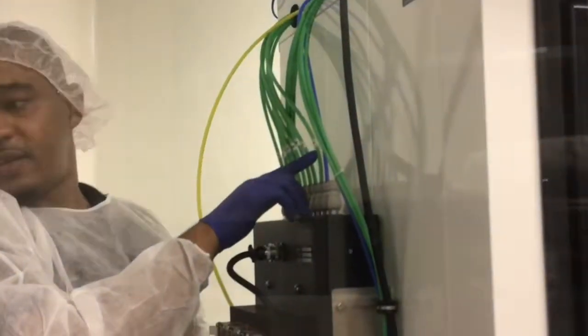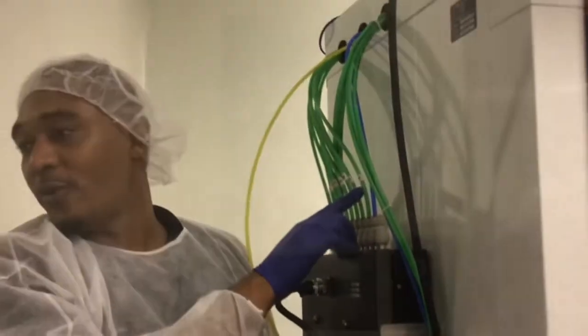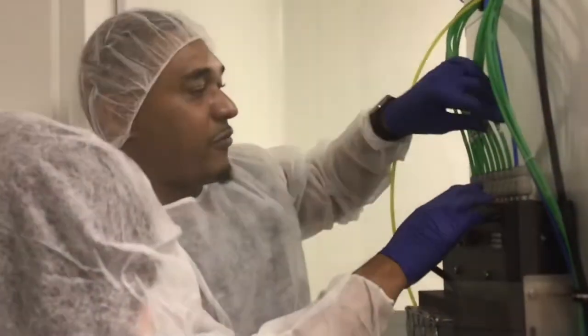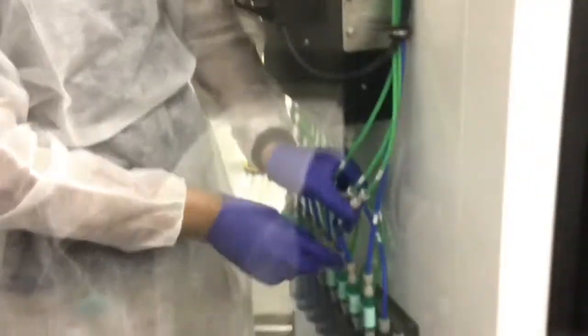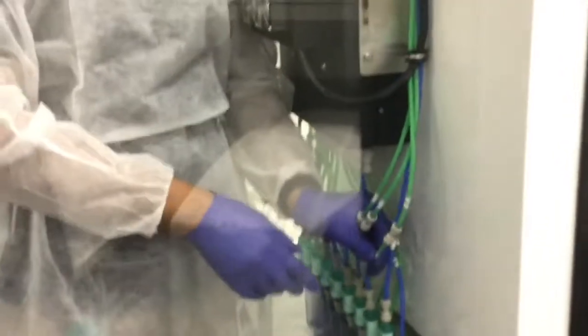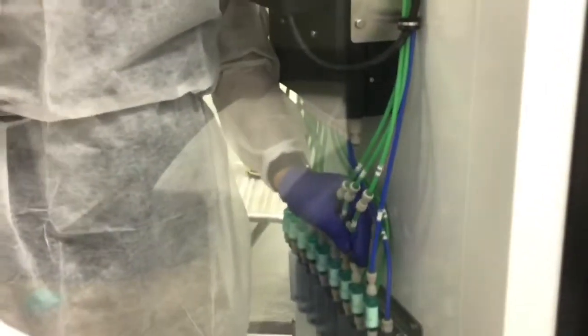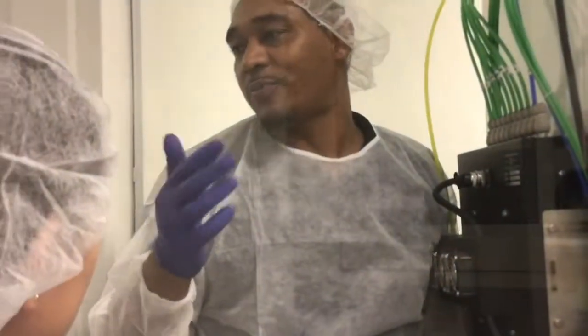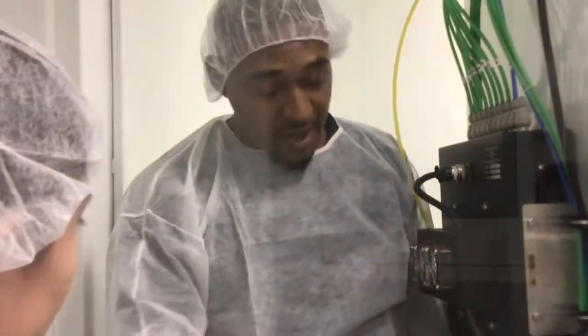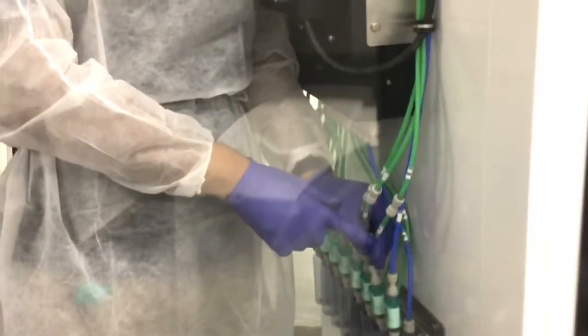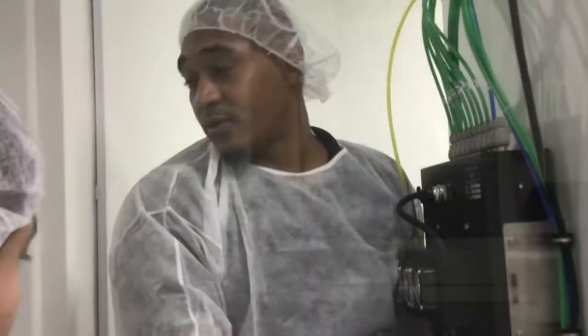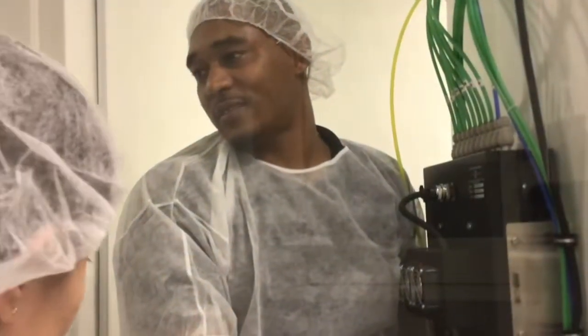So it could suck air straight from the room instead. Yeah, you want it sucking air from the cage. These pieces here are called restrictors. We have this pump that is sucking air, and we're telling it to suck 0.6, but again, it's a pump, so we believe it's somewhere a little more than 0.6. This guy is the one that regulates it to 0.6, to get it pretty close to 0.6.